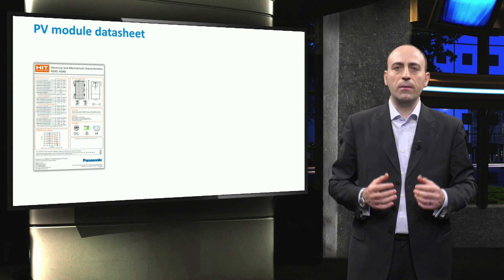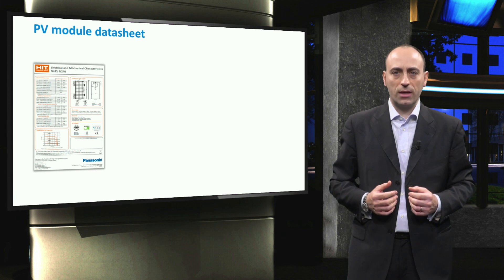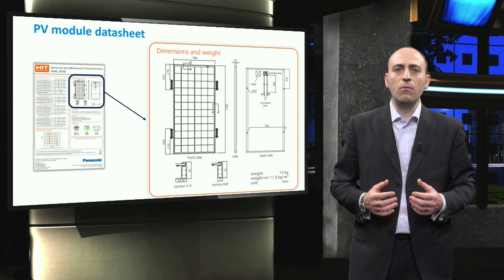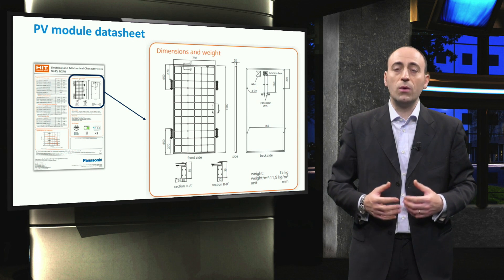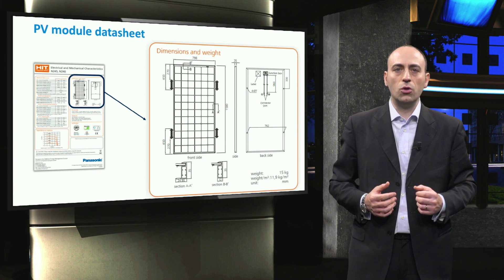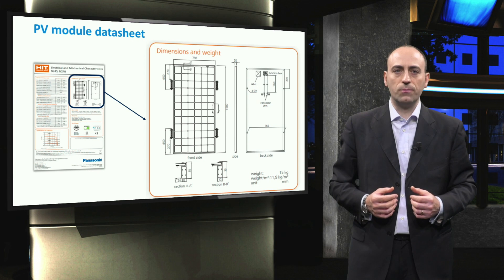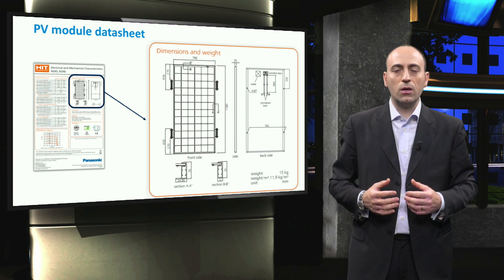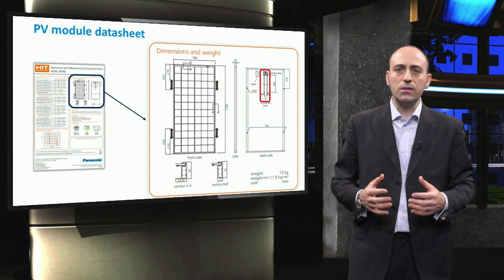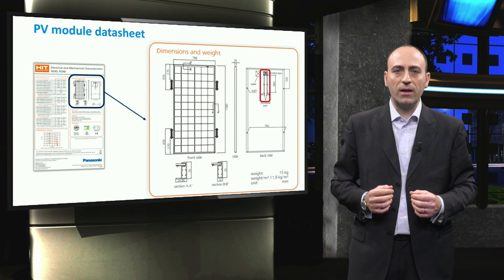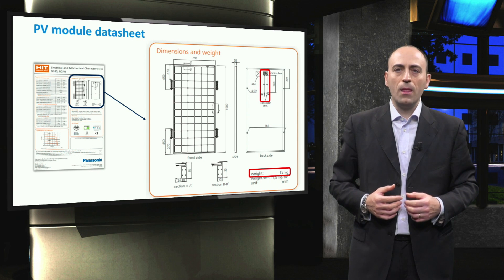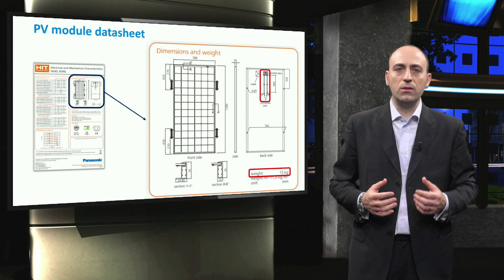This is the datasheet of a PV module by Panasonic based on heterojunction technology. The enlarged area indicates the dimensions and weight of the PV module. The dimensions of the PV module are important for PV system design, in order to estimate the total irradiance incident on the module and the space required for the installation. Starting from the left-hand side, we have front side and back views of the PV module, including the frame and the junction box. The junction box is represented by the little square on top of the back view with the connectors attached to it. The weight of the module can be found underneath this figure. The weight can be an important property if the area on which the modules are installed has limited weight-bearing capacity.